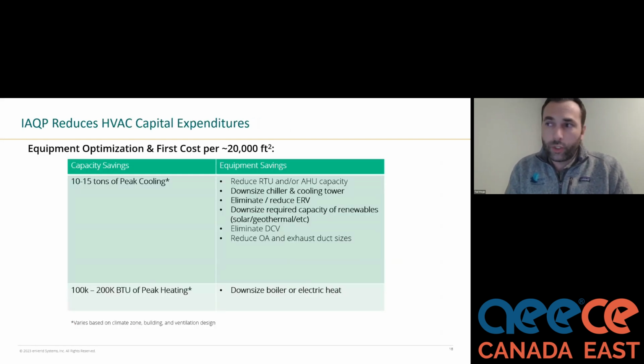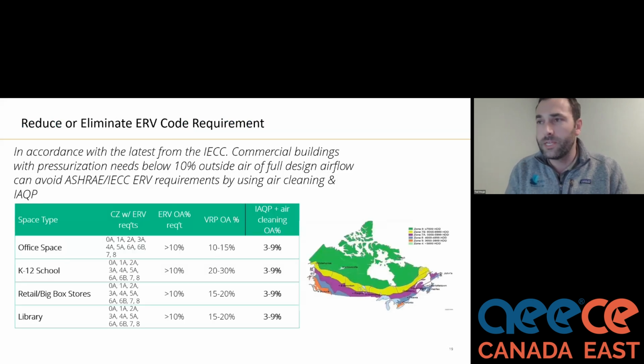In terms of what a 20,000 square foot building might look like, each time you deploy this solution, you might be shaving off 10 to 15 tons of peak cooling and several 100,000 BTUs of peak heating as well. And this enables us to downsize the chiller, eliminate or reduce energy recovery, and downsize required capacity of things like geothermal, where we've seen a lot of great case studies where geothermal well fields actually shrink in size. There's big first cost savings there.